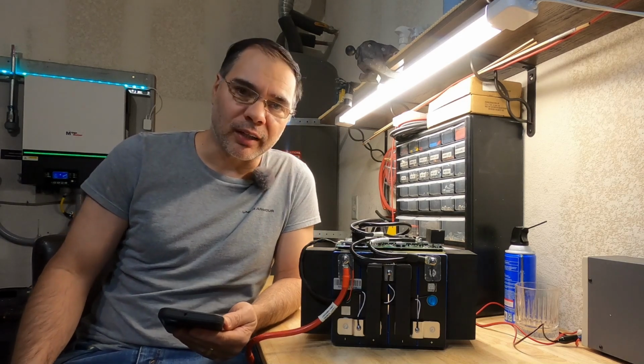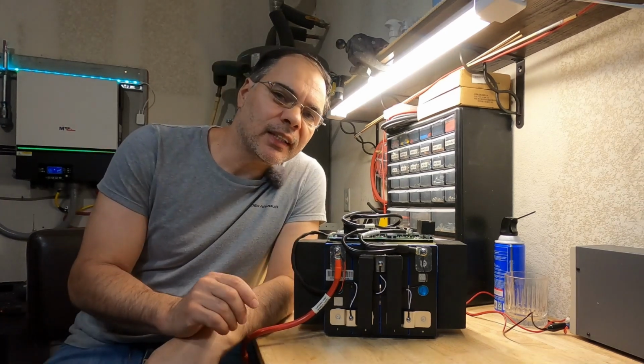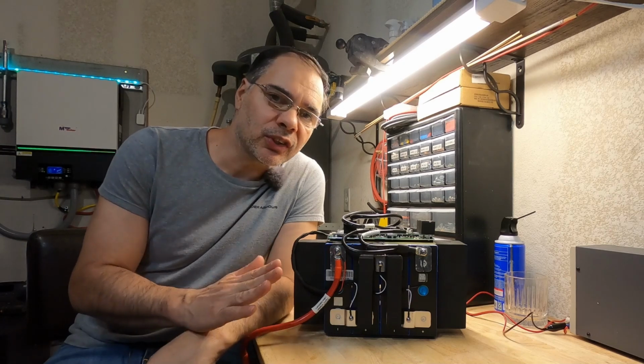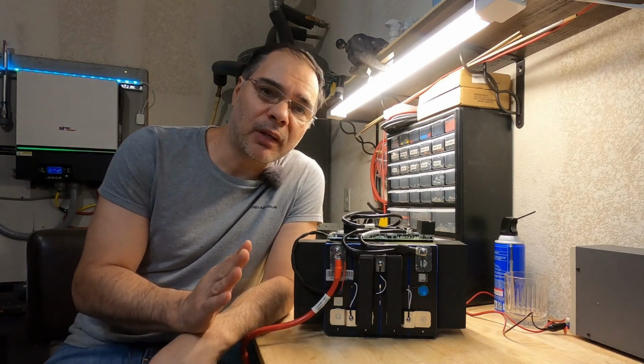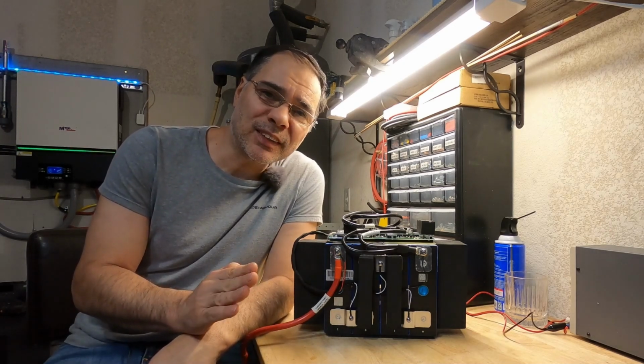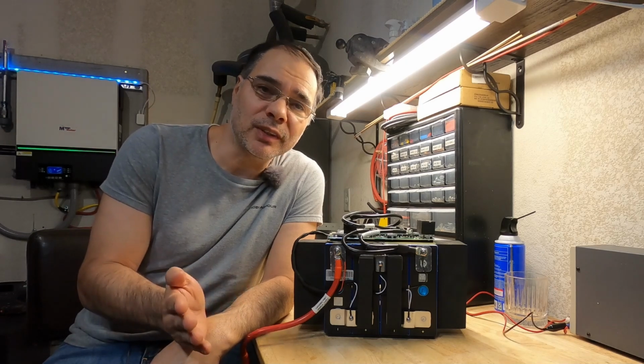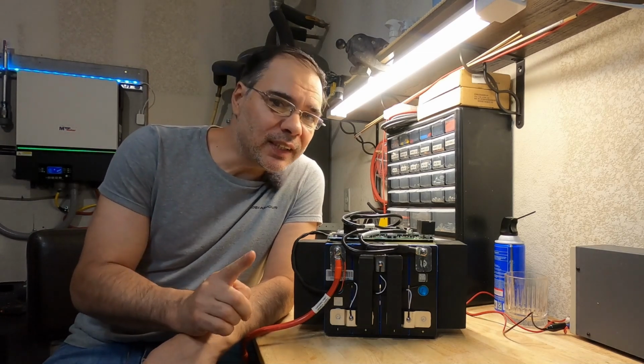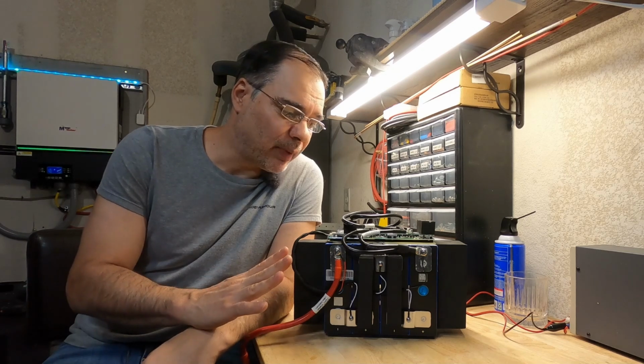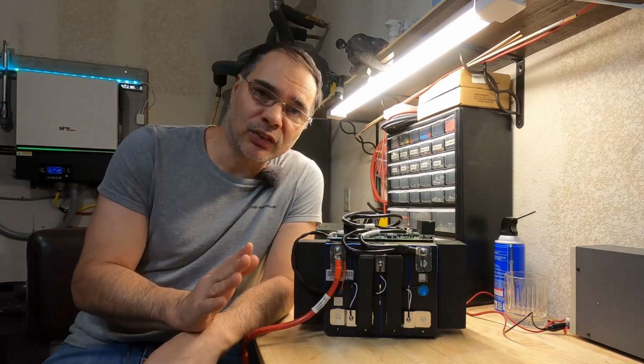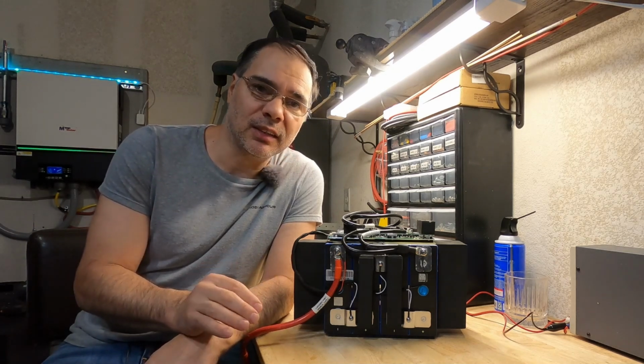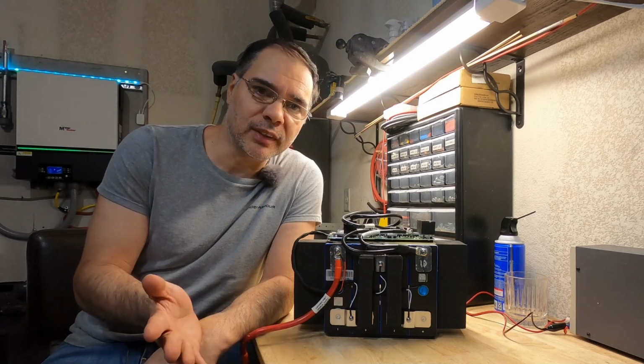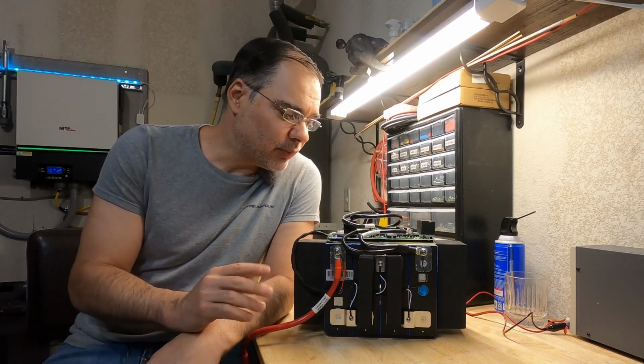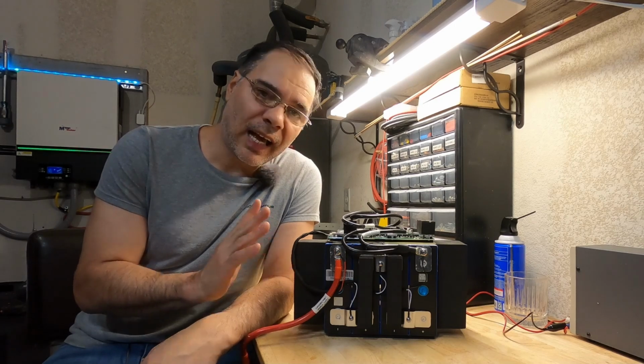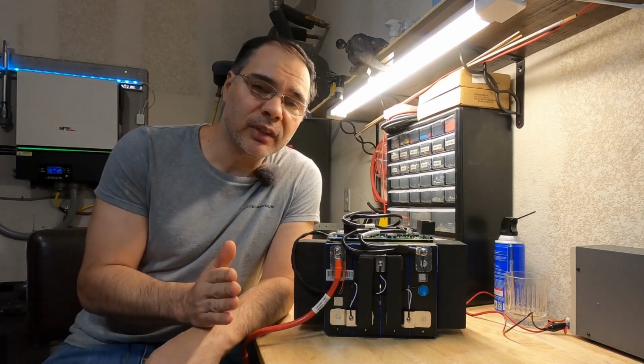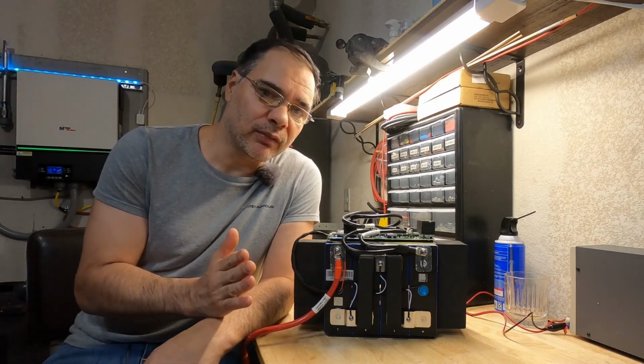Both good products. So they told me that this battery does have low temp cutoff, but the early versions of this battery have the low temp cutoff set to -20 degrees, basically making it useless. If you do need low temp cutoff, the newer versions have corrected that setting to 0 to 2 degrees Celsius, that's basically freezing, and that's where it should be. So just make sure, if you order this battery and need low temp cutoff, ask them if you get the corrected version.